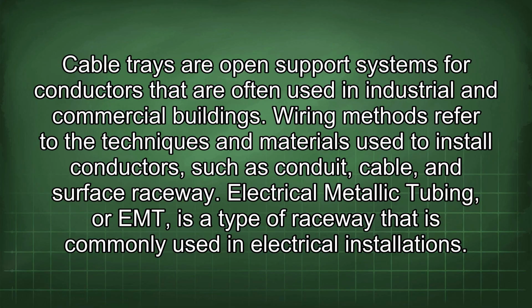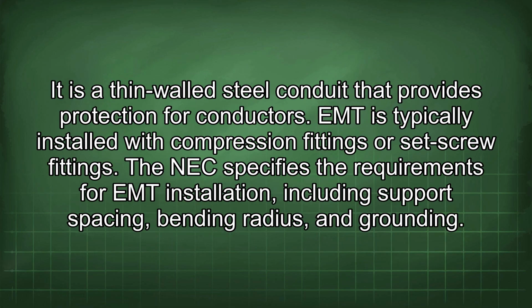Wiring methods refer to the techniques and materials used to install conductors, such as conduit, cable, and surface raceway. Electrical metallic tubing, or EMT, is a type of raceway that is commonly used in electrical installations. It is a thin-walled steel conduit that provides protection for conductors. EMT is typically installed with compression fittings or set screw fittings. The NEC specifies the requirements for EMT installation, including support spacing, bending radius, and grounding.